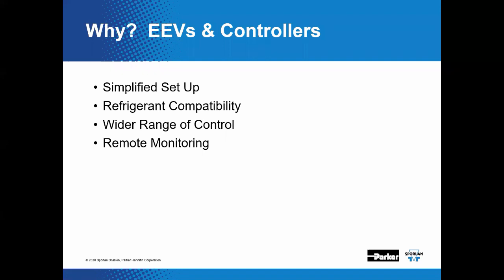In the event that there's a refrigerant retrofit that's getting done, and how often does that come up, Glenn? It's coming up more frequently as we go through life, Jim. So in a retrofit situation, there's generally no need to change components, provided the control accommodates the new refrigerant. TXVs are refrigerant sensitive: thermostatic charges, valve capacity. That all has to be taken under consideration when you're selecting a thermostatic expansion valve to control superheat at the bulb.